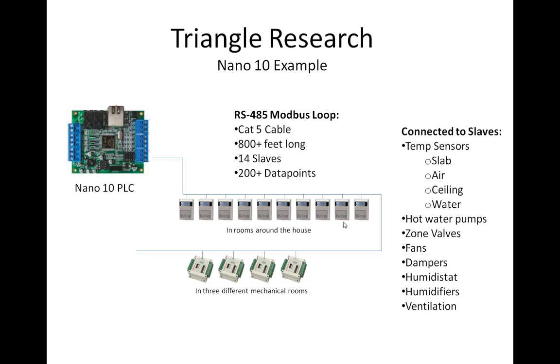We're also measuring water temperatures of different storage tanks. The output devices are controlling the hot water circulation pumps, the zone valves, fans, dampers, humidistats, humidifiers, and ventilation. So the Nano 10 collects all of the data from this network, goes through its logic sequence, and then turns all the appropriate things on or off, depending on what needs to be done.